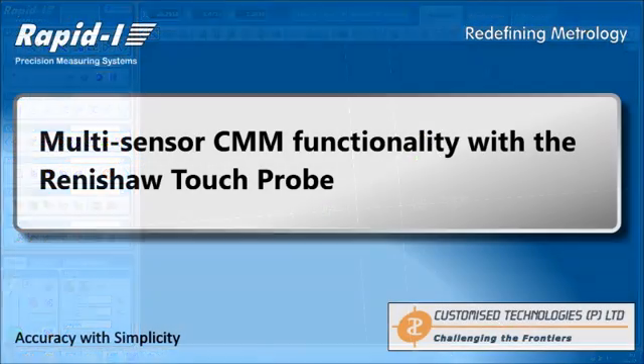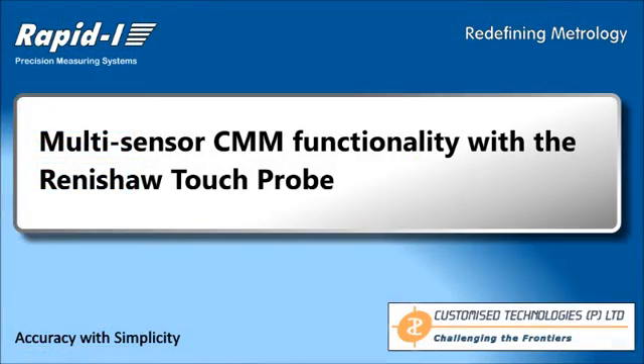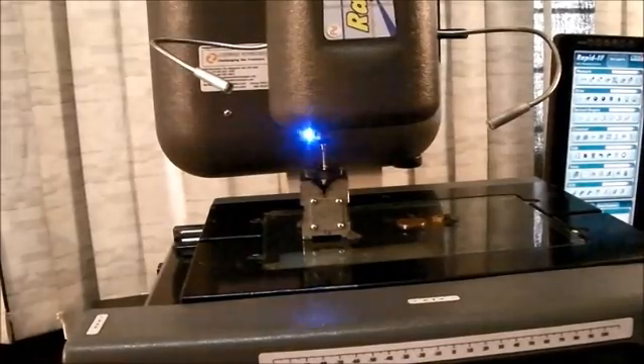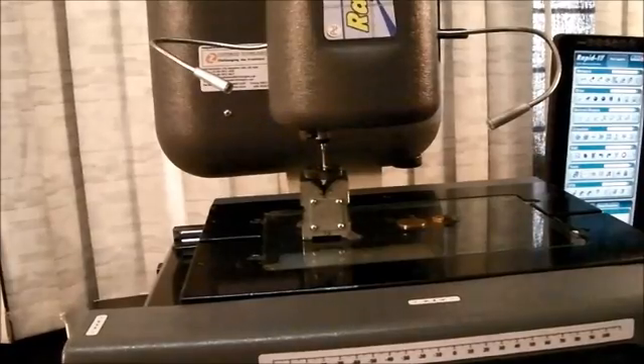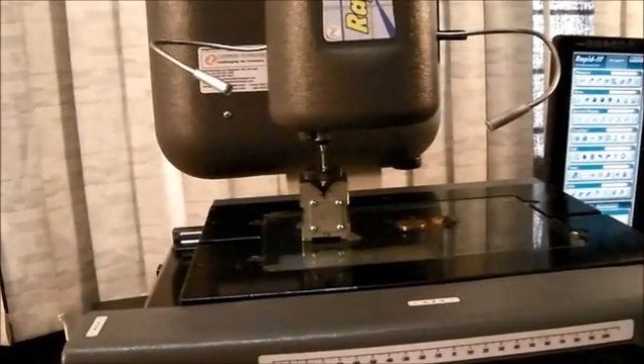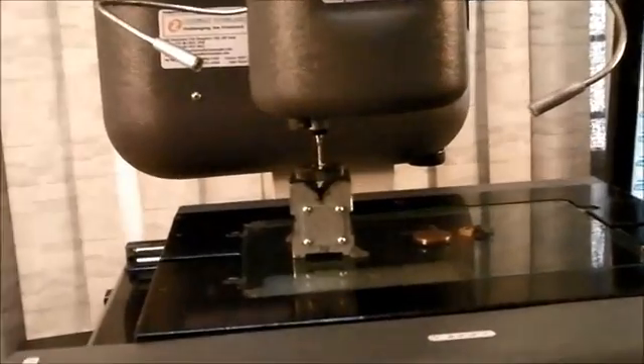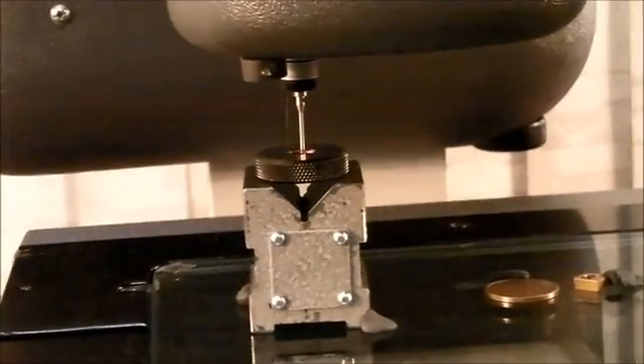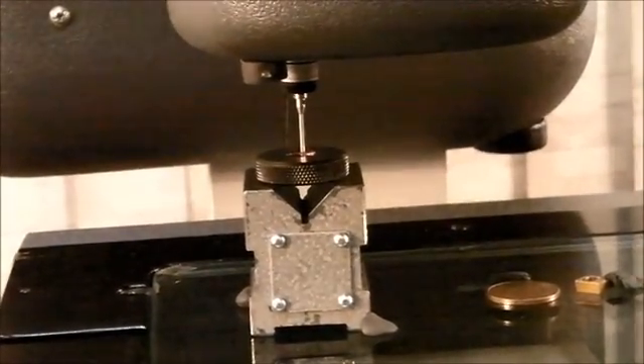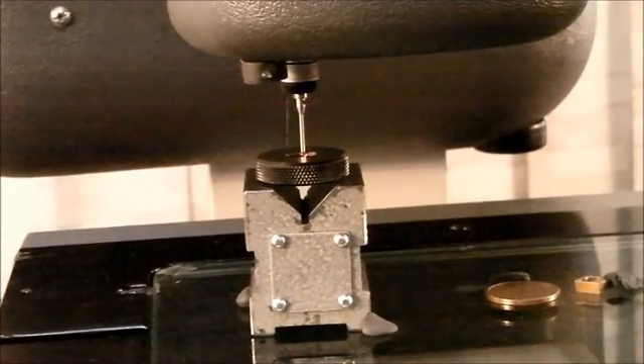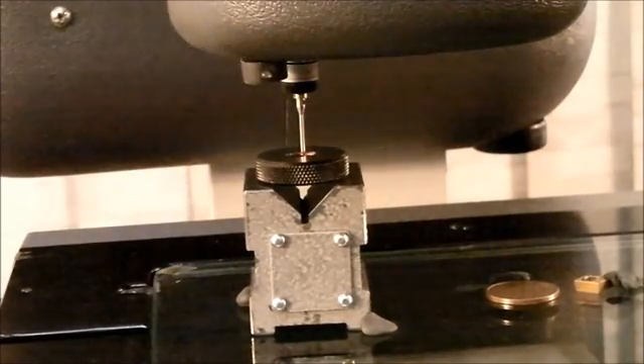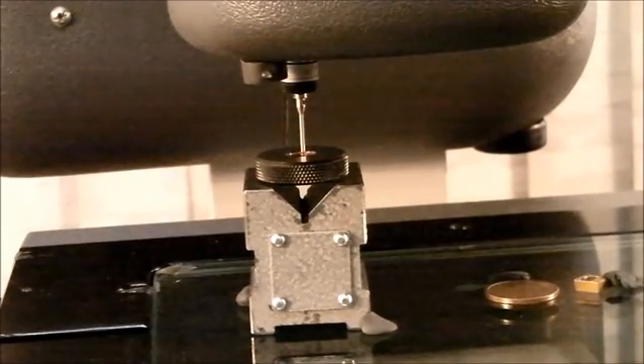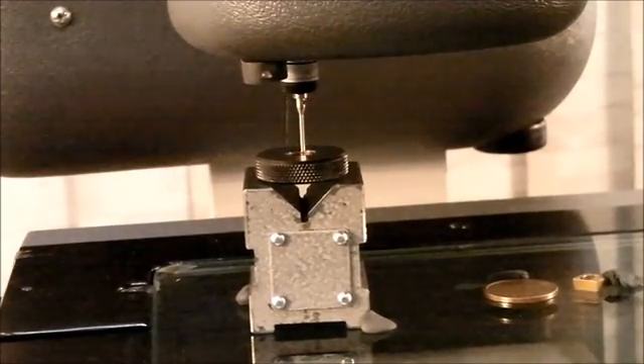The final feature in this video is going to be the CMM functionality built in with Renishaw touch probe integrated with Rapid-I. Here you see the standard Renishaw TP20 touch probe doing a cylinder measurement on a simple ring gauge.